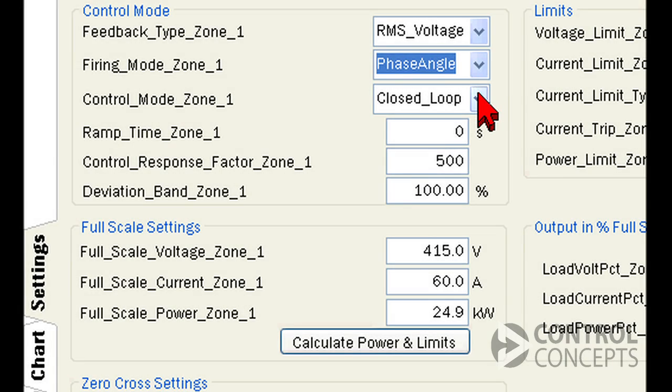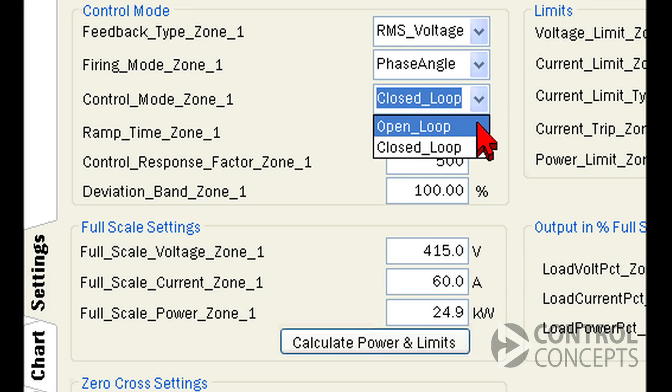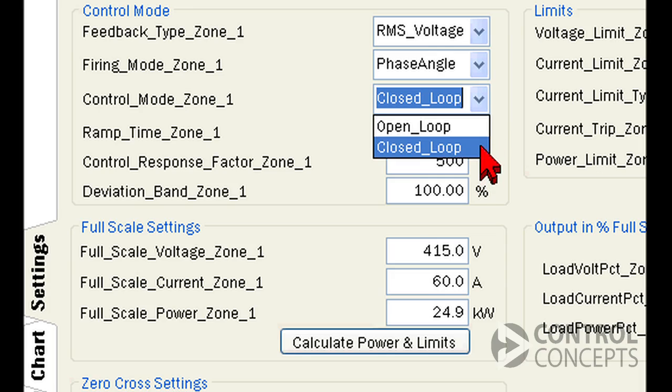For your control mode, you can choose between open loop or closed loop. When closed loop is selected, the processor uses the feedback and automatically adjusts SCR turn on time to achieve a certain set point. This mode is usually preferable because it maintains an accurate set point, while open loop is typically only used for diagnostic purposes. For more information, contact the factory or refer to the control panel manual.